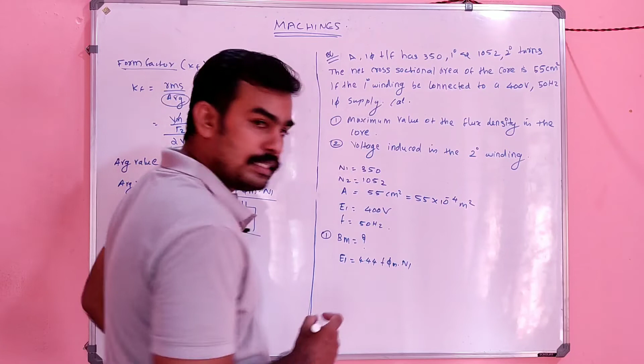So what do we have to find? The maximum value of the flux density in the core, that is Bm. For that we can use the equation E1 equal to 4.44 F phi m N1, that is the RMS value. In problems, unless it is mentioned as average, we normally work with the RMS value. Bm is nothing but phi m by A, since flux density is flux per unit area. So phi m is replaced by Bm into A, and it becomes 4.44 into F into Bm into A into N1, correct?